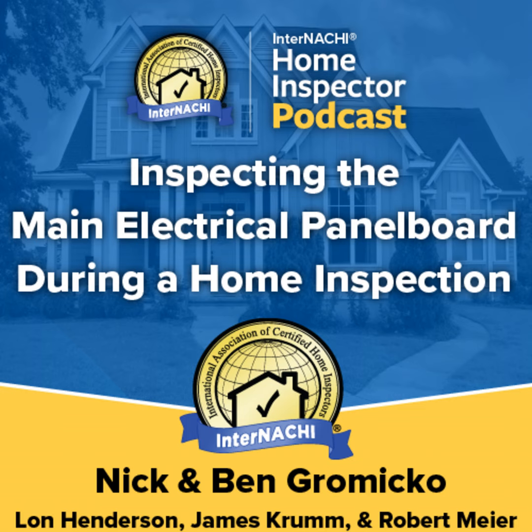Adequate space should be provided around the electrical panel board for safe access to the components. Please refer to the InterNACHI illustration for panel board working space and clearances found in this article online. Generally, the working space in front of the panel board must be at least 36 inches. The working space must be at least 30 inches wide in front of the electrical panel board and at least 6.5 feet in height. Panel boards must not be located in bathrooms, toilet rooms, clothes closets, or over the steps of a stairway. The overcurrent devices must be readily accessible.